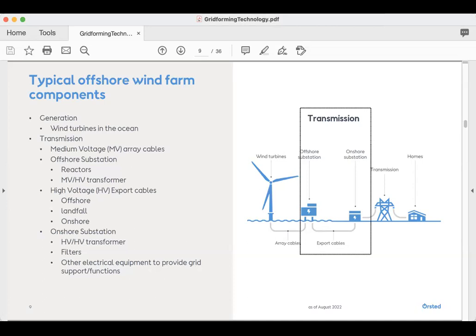Most often the wind turbine has its own step-up transformer that converts to medium voltage, typically around 66 kV for most of our offshore wind farms in the US. Then there's an offshore substation, shown in the picture, which transforms the medium voltage to high voltage.